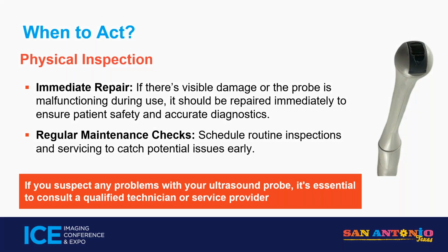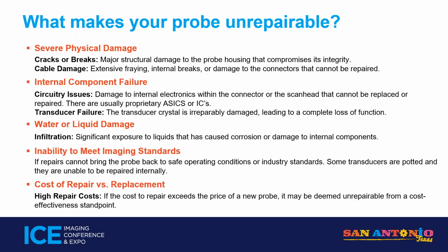What makes your probe unrepairable? Severe physical damage, and it is severe at this point. I mean, if it's a cracked case, we can fix it. But if it's a cracked case that you've let sit there for 3 years, and now you've had fluid intrusion sitting in there, and all the cable is corroded, all the connections are corroded, all the electronics are basically failing, we can't fix everything in a probe. It's not repairable. Then we just tell you to buy a new probe.